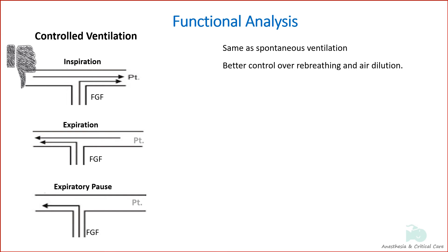Mapleson E provides a low resistance flow during controlled breathing owing to the large reservoir tube along with the absence of the APL or expiratory tube. The system also has low dead space as the fresh gas inlet is located near the patient end.